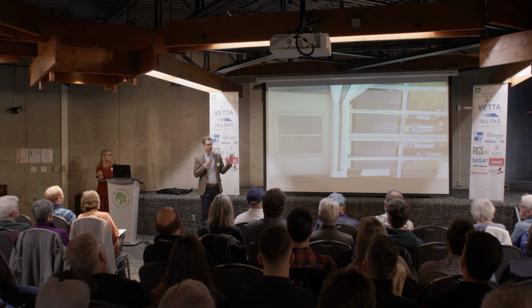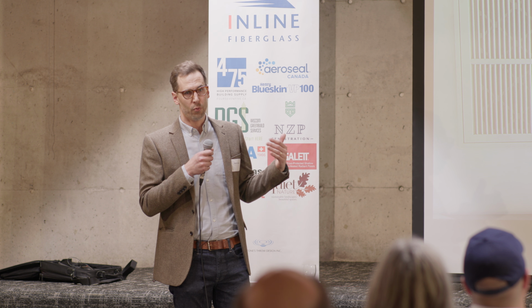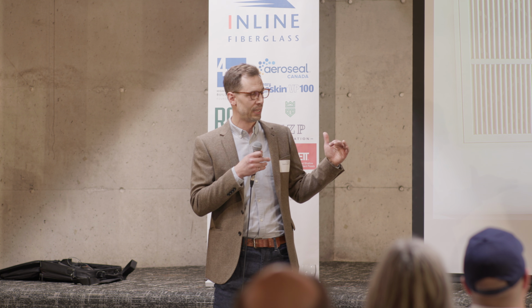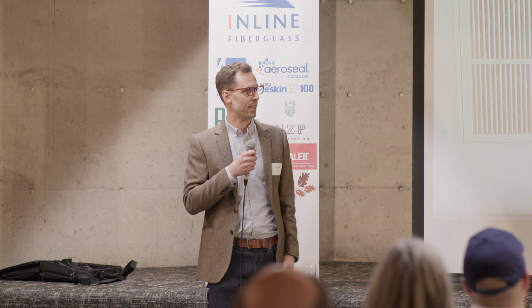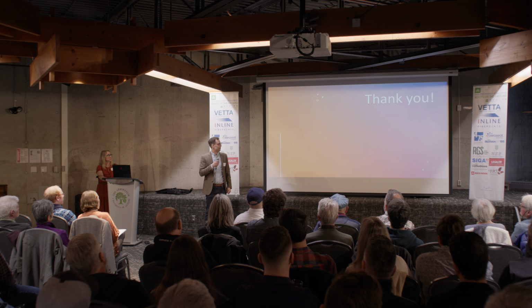Never have to try to find them, because that can be challenging. But now for the life of the building, you're ordering stock 24 by 24 by 2 inch pleated MERV 13 filters, which are really easy to come by. They're interchangeable, and when you oversize them like that, you slow down the air and the pressure drop is pretty much negligible. So yeah, that's it.